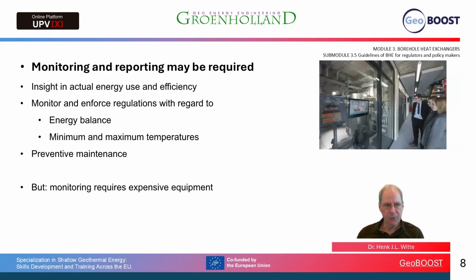In a number of cases, monitoring and reporting may be required. In the Netherlands, for instance, we have a monitoring obligation for all systems with the exception of single-family households. And this will provide insight in the actual energy use and efficiency, which you can feed back into the design loop. And it is also used to enforce regulations with regard to energy balance, minimum and maximum temperature. Monitoring, of course, can also be important for preventive maintenance because it will tell you how the system is operating and gives you the possibility to check before you go to site, and maybe you know already that a temperature sensor needs to be replaced. However, on the other hand, monitoring does require somewhat more expensive equipment, so it increases the total cost of the system, and for smaller systems this can be a significant burden.